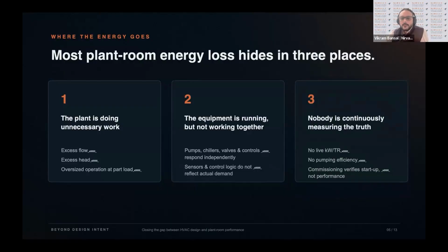I don't find anybody working on the kilowatt per ton of the plant room. We talk about kilowatt per ton of the chillers, but we are not talking about the kilowatt per ton of the entire plant room, which is working as a system to feed the entire building. The individual equipment is getting monitored and rectified, but not as a system.